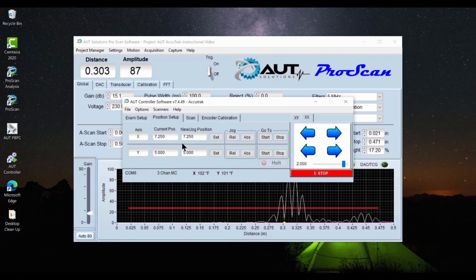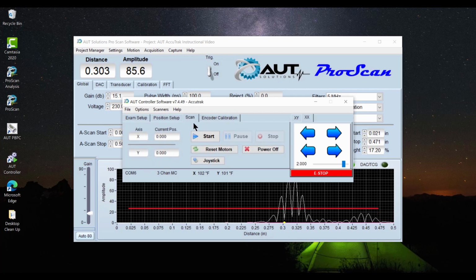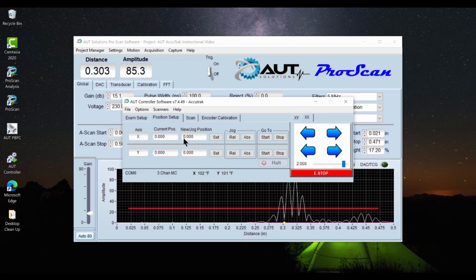Our scanner is currently set to 0, 0 on X and Y. So we will go in and zero out the X by typing in 0, clicking set. And our Y is at 0, so we will do 0 and set. Now if you do see any negative numbers or any variables in here that just change without the scanner moving, you might want to come over to scan, click reset motors, and you will notice we have some negative values pop in as the encoder boards on the motors themselves are resetting. So now you will notice when you go back to position, you're at 0, 0 yet again.